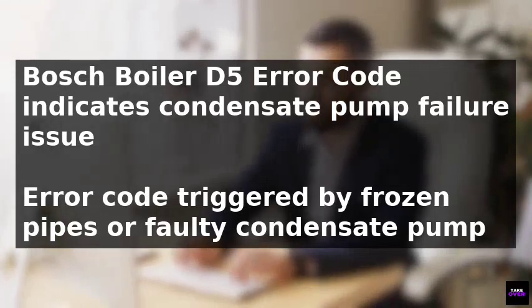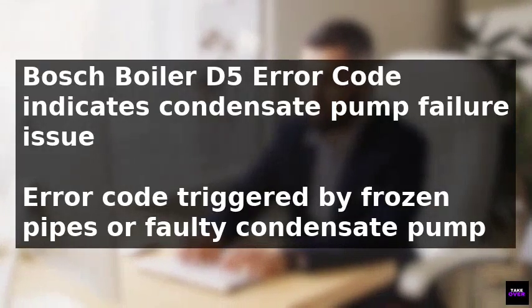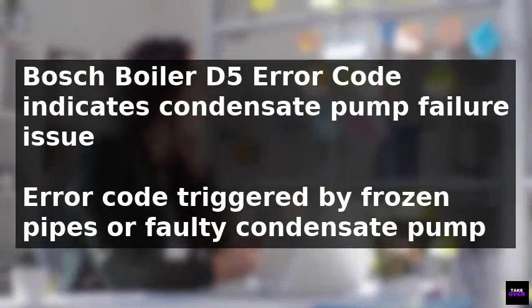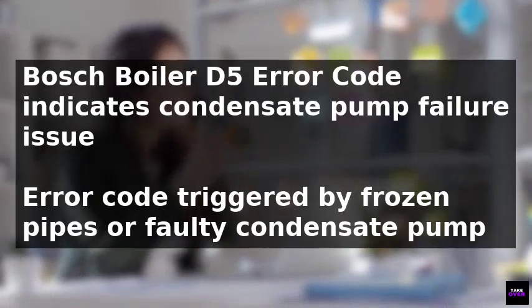The Bosch boiler's D5 error code is displayed when the boiler detects a condensate pump failure. This error code is typically triggered by common issues such as frozen condensate pipes or a faulty condensate pump. To resolve the issue, it is recommended to start by unfreezing the condensate pipes.